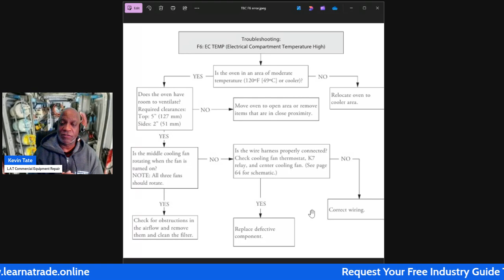Either way, you'll want to trace those wires just to make sure you have a good connection, and that the K7 relay is not damaged. If that K7 relay has damage to any of the contacts, that's probably why you're not getting power to the fan to turn it on, if the fan is in good condition.